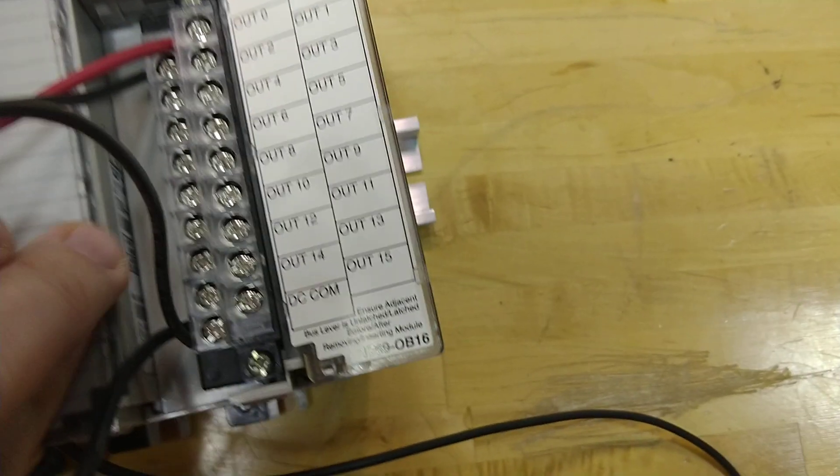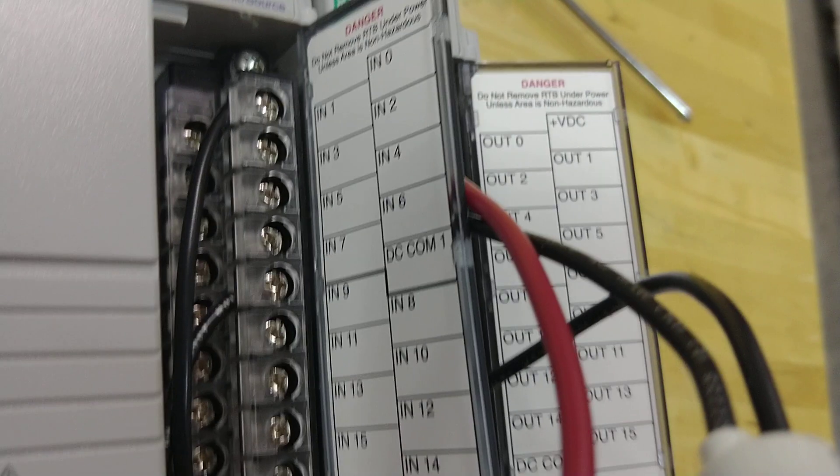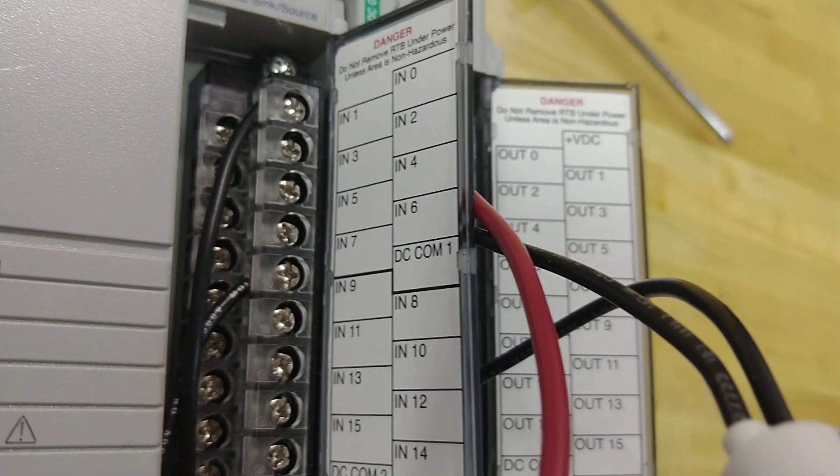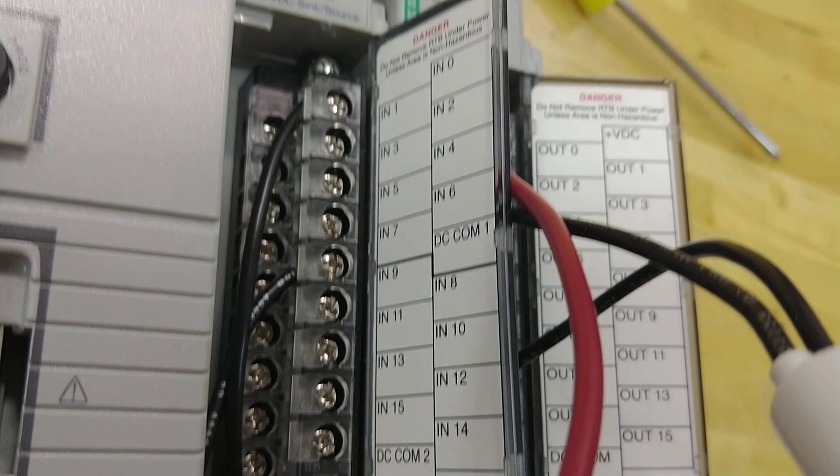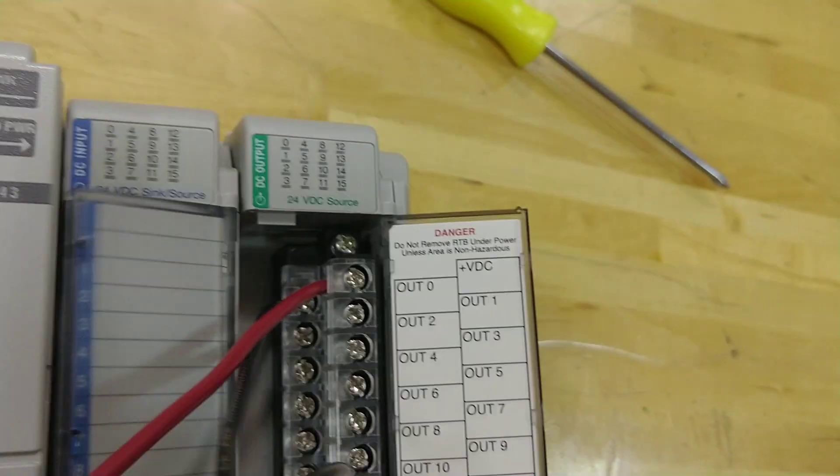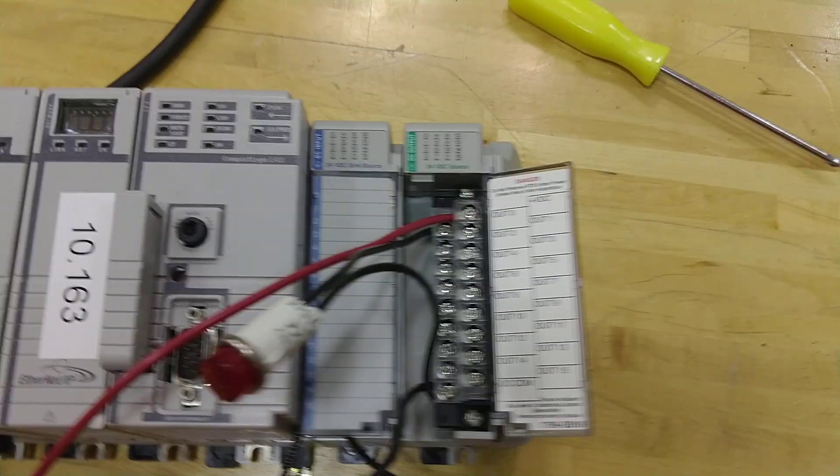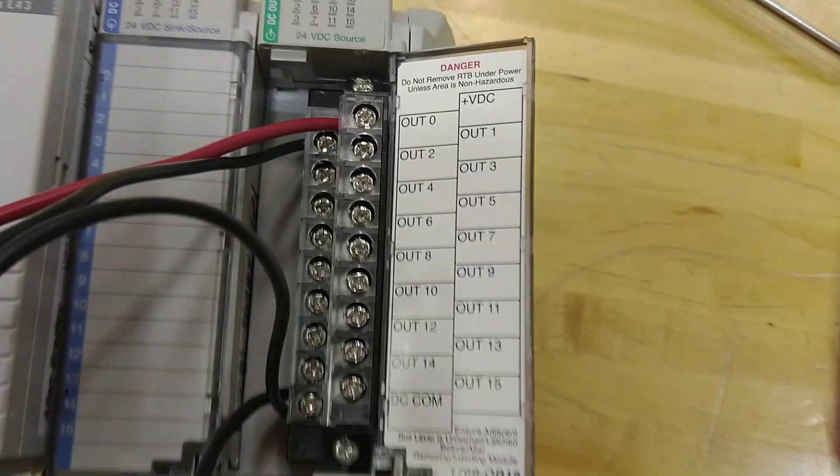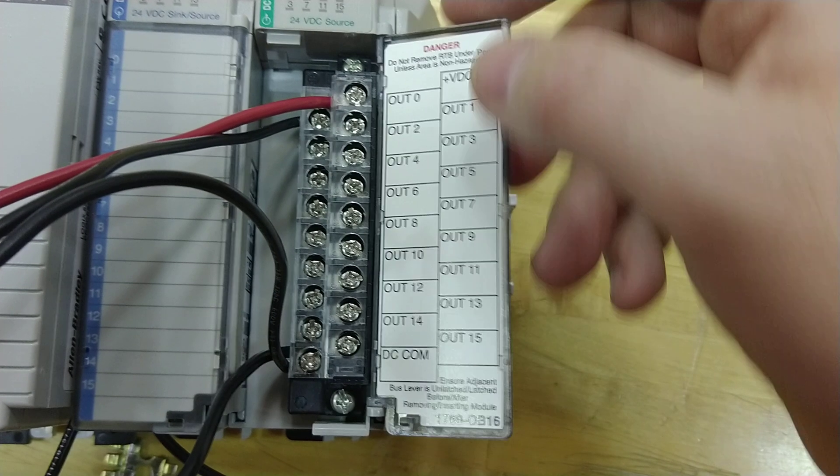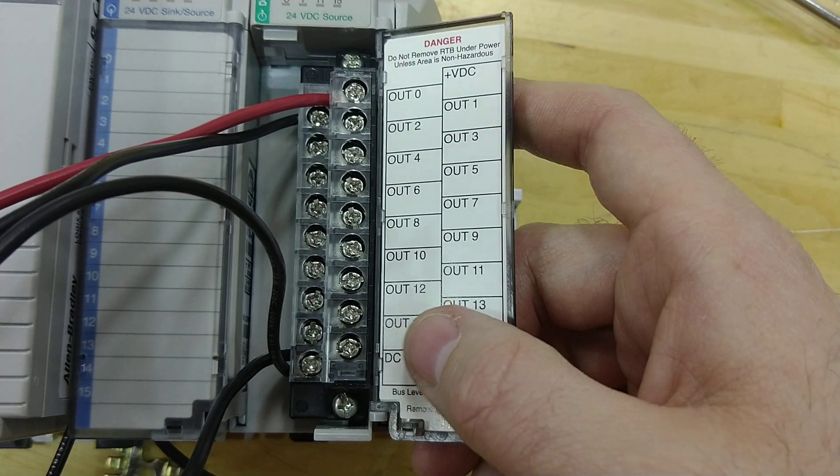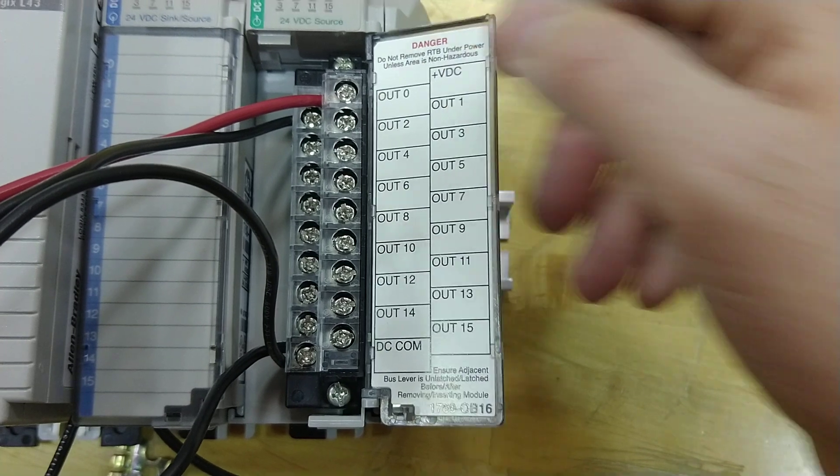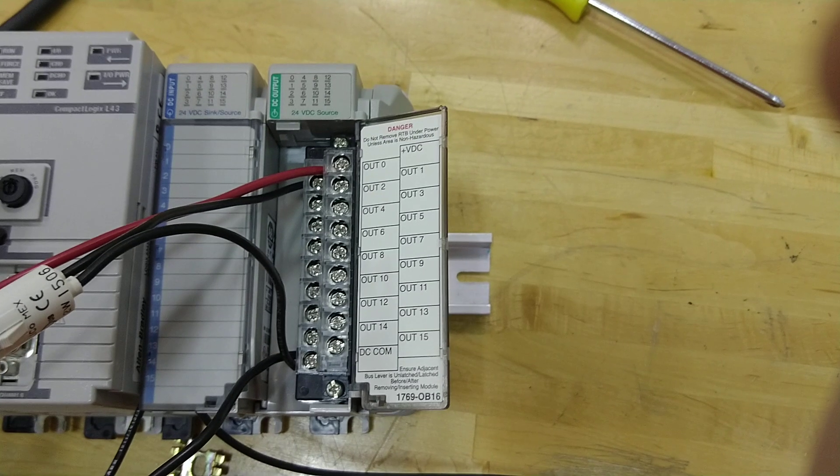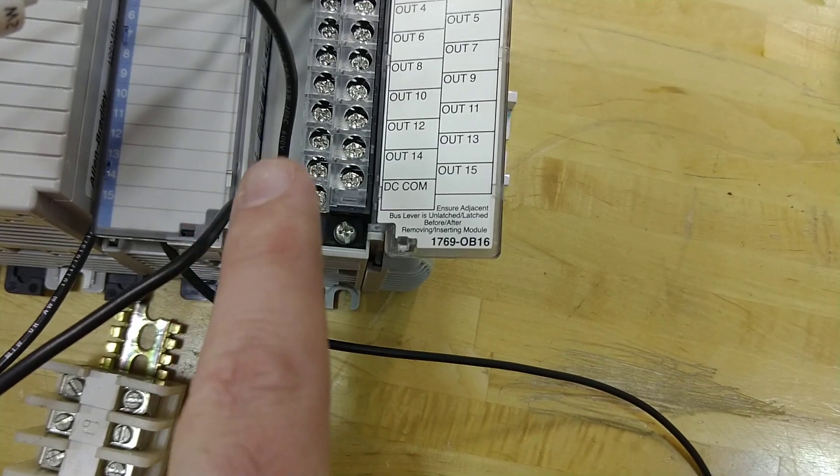Same is true for my inputs. If I open it up, and I did this wrong, you can see the same thing. There's a DC common 1 and a DC common 2, and an input. So I have to supply the common and the ground. In the case of this card, I supply the common and the ground to help power the card. Just keep that in mind, and in this case, just tie everything in.